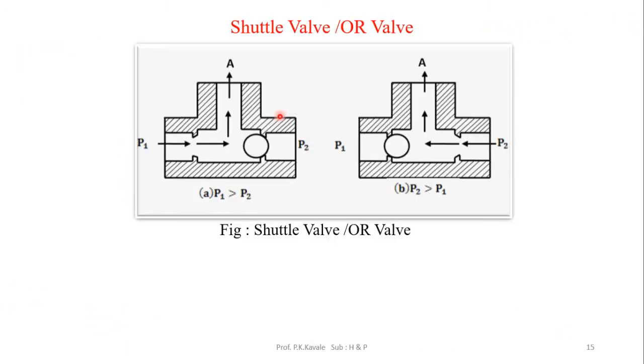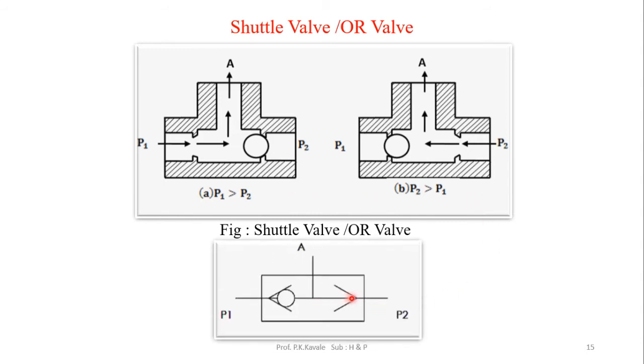The shuttle valve: the valve body has two inputs, P1 and P2, and one output, A. The restrictor is a ball type. If input P1 is present, output is given. If P2 is present, output is given. If both are present, the ball remains at the center and flow goes from P1 to A and P2 to A. It is also known as the OR valve.